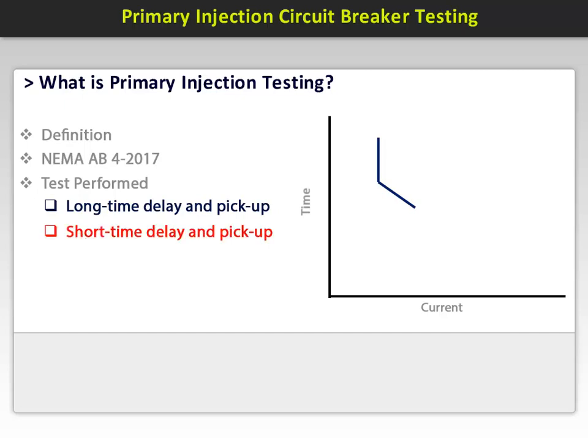Next is the short time delay and pickup, represented by the red line on the curve. This is an intentional preset delay to provide coordination with other protective devices. The test current is usually 1.5 to 2.5 times the short time pickup and is injected in each pole of the breaker, and the trip times are recorded. Typically the results are in milliseconds.